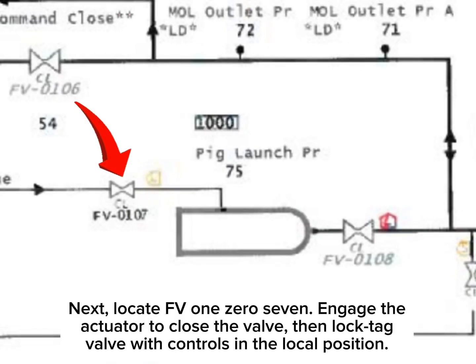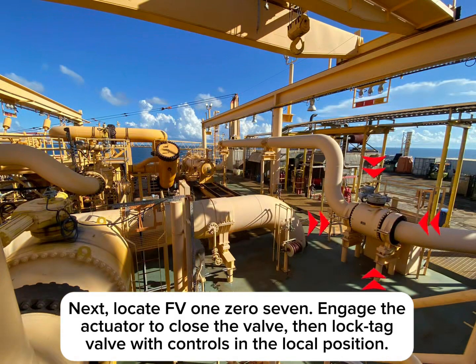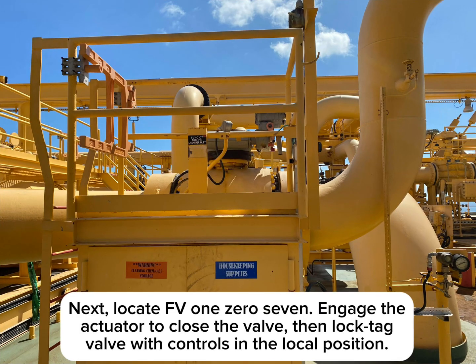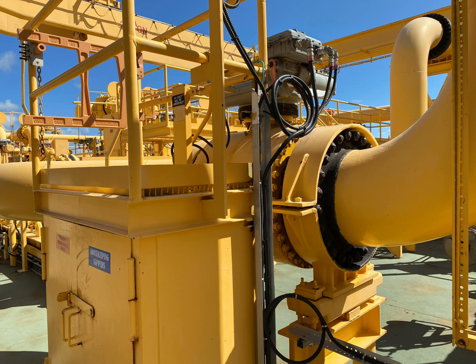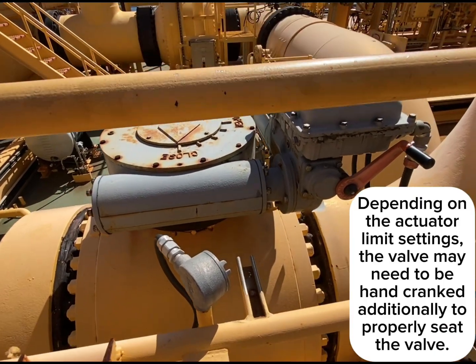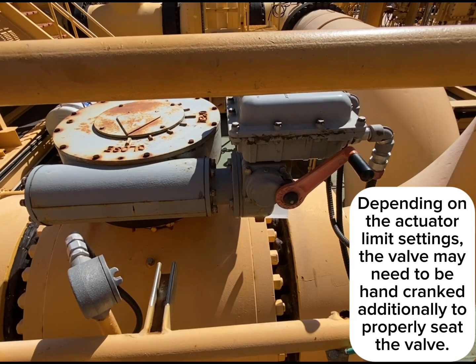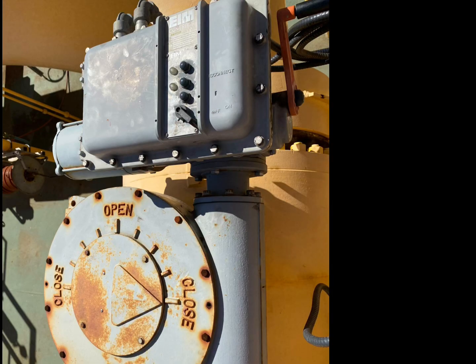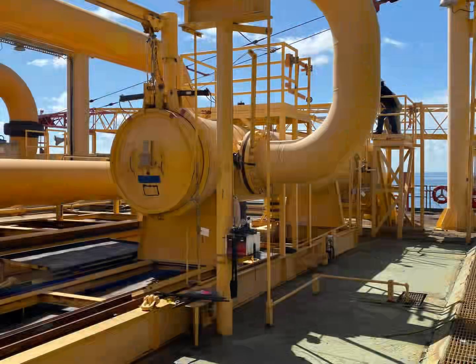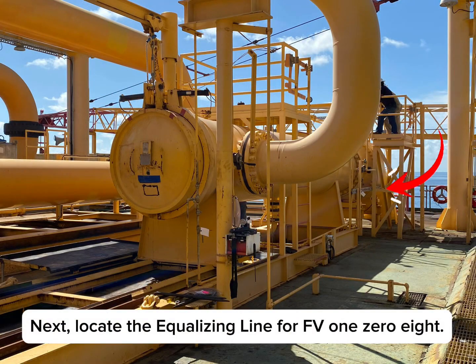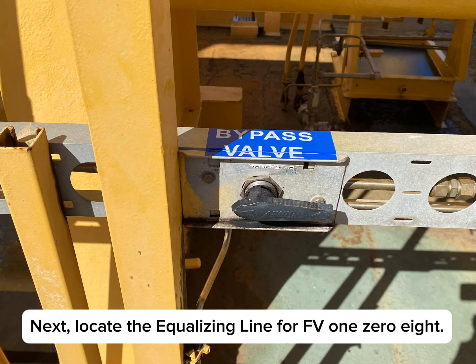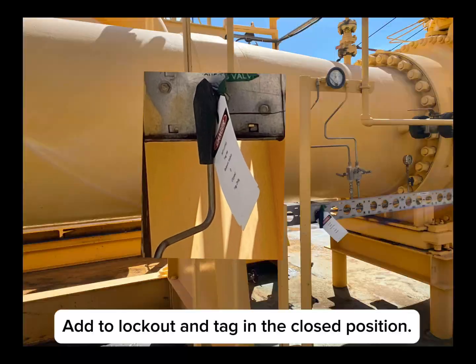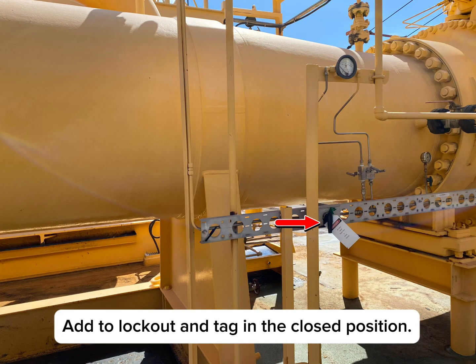Next, locate FV107. Engage the actuator to close the valve. Then lock and tag the valve with controls in the local position. Depending on the actuator limit settings, the valve may need to be hand cranked additionally to properly seat the valve. Next, locate the equalizing line for FV108. Add the lockout and tag in the closed position.